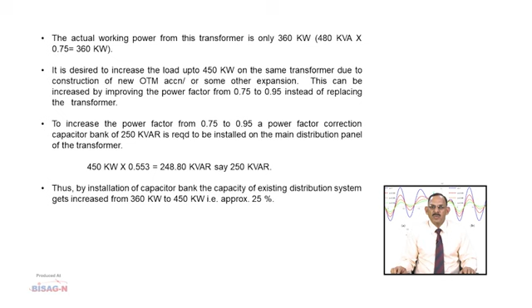To increase the power factor from 0.75 to 0.95, a power factor correction capacitor bank of 250 kVAr is required to be installed on the main distribution panels of the transformer. 0.553 is the multiplying factor. 450 kilowatt into 0.553 equals 248.80 kVAr, say 250 kVAr. The factor 0.553 is obtained from the multiplying factor table. Thus, by installation of capacitor bank, the capacity of the existing distribution system gets increased from 360 kilowatt to 450 kilowatt, that is approximately 25%.